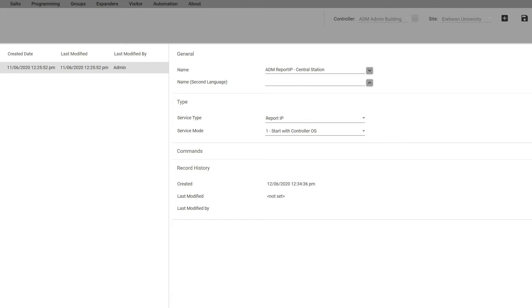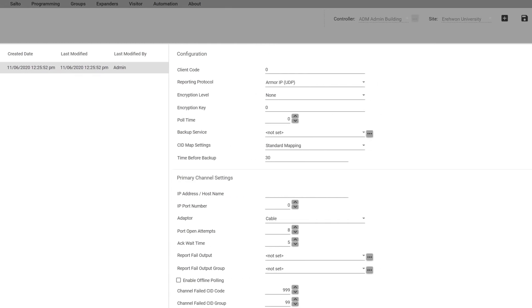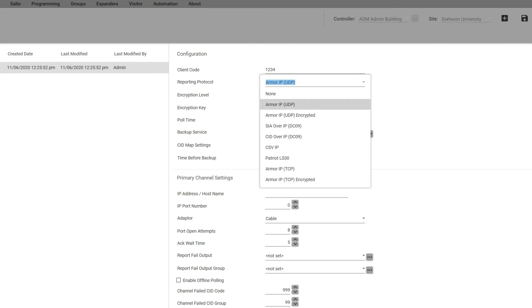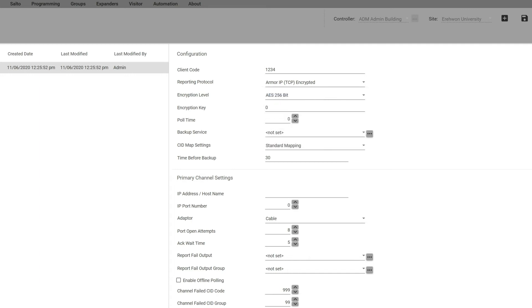In the general here you're going to see again a client code, it could go up to eight digits, just depends on what the company gives you. In the reporting protocol, if you are using our version here it's Armor IP. If you do use some third-party IP solutions we can accommodate some of those here. And encryption level, if the IP monitoring station has a certain kind of encryption, you want to pick which kind that they're encrypting with. Then they're going to give you an encryption key you want to put that in there, so that's again between you and the monitoring station what that's going to be.